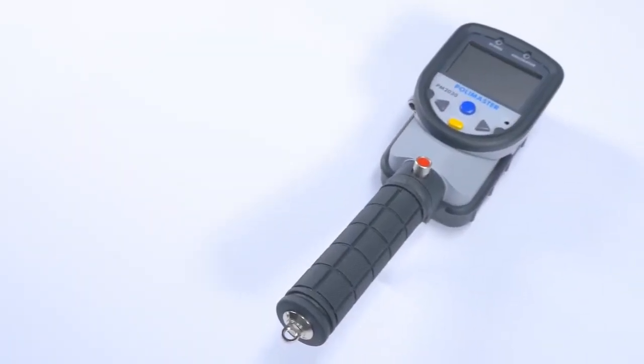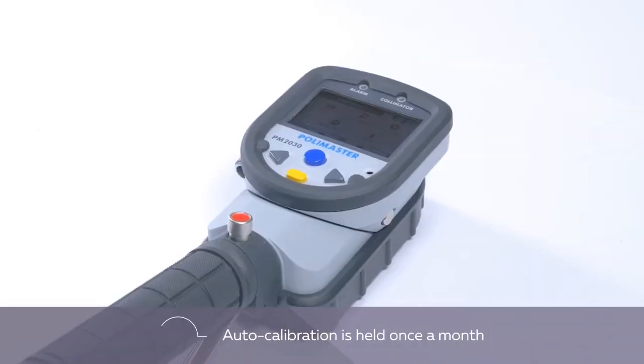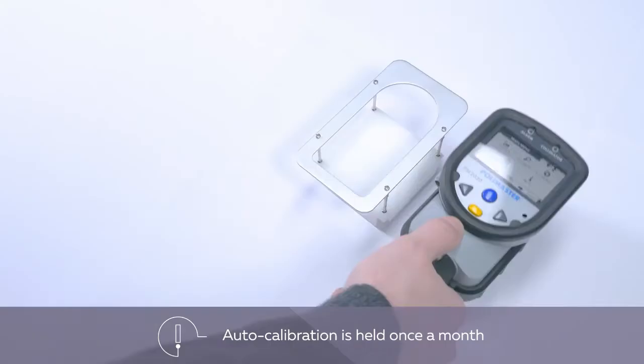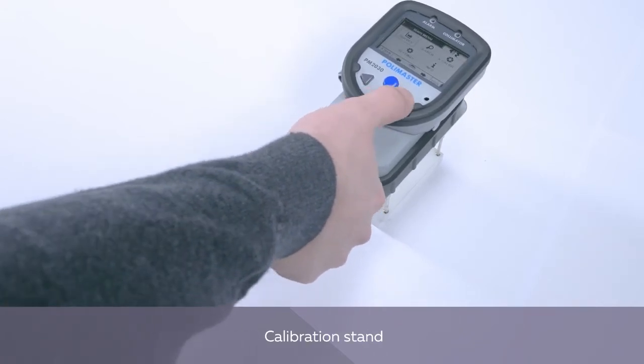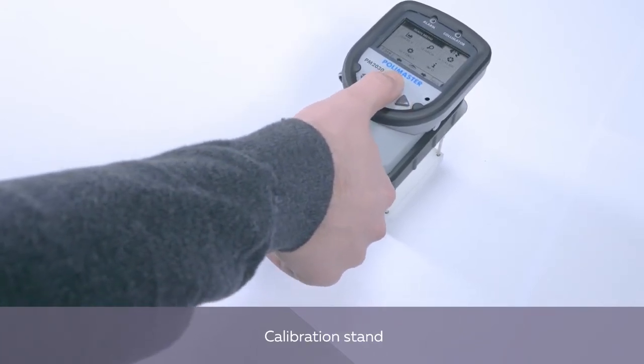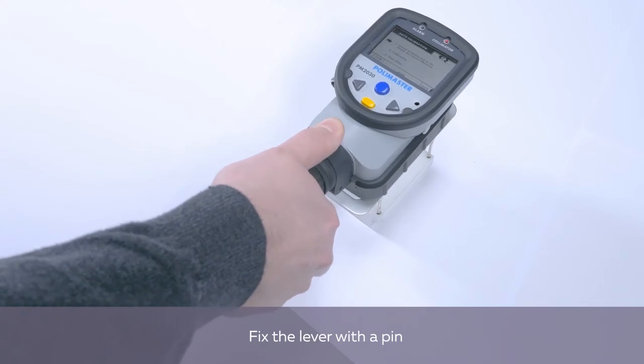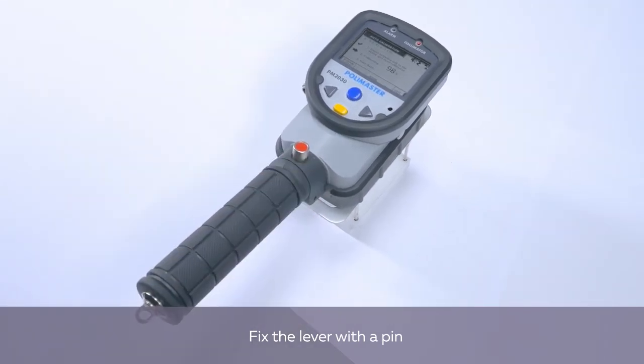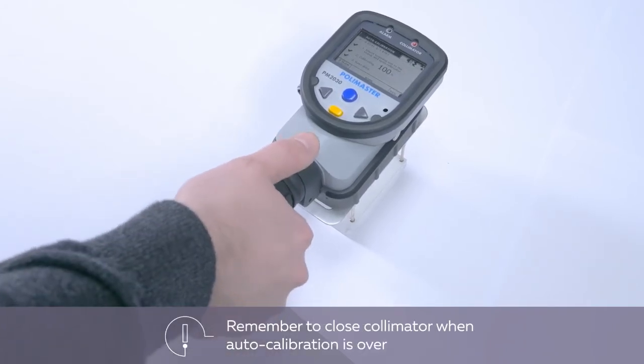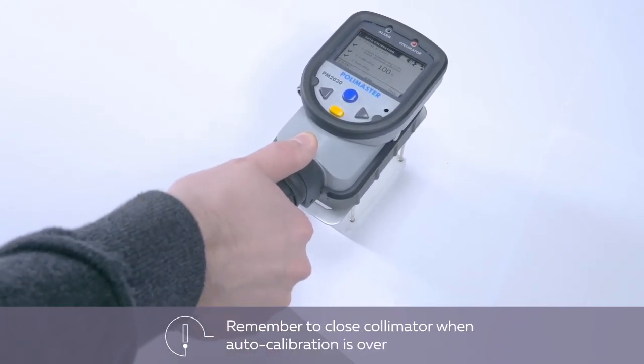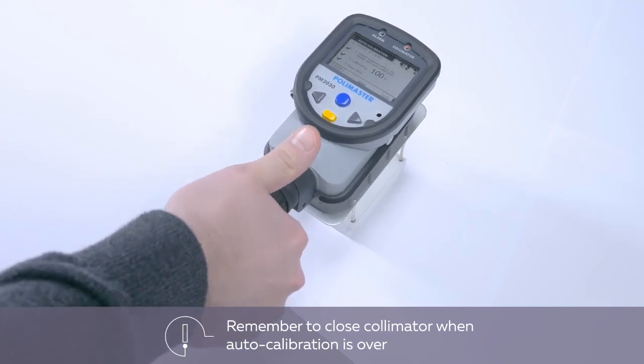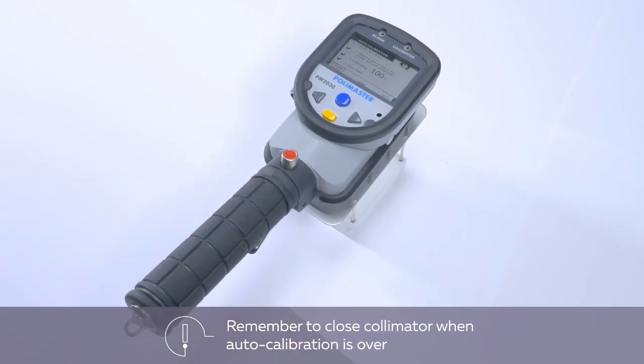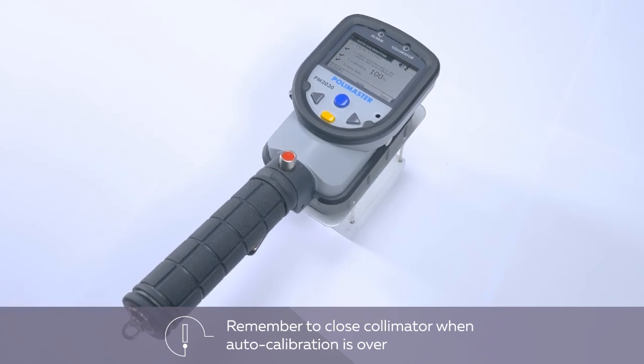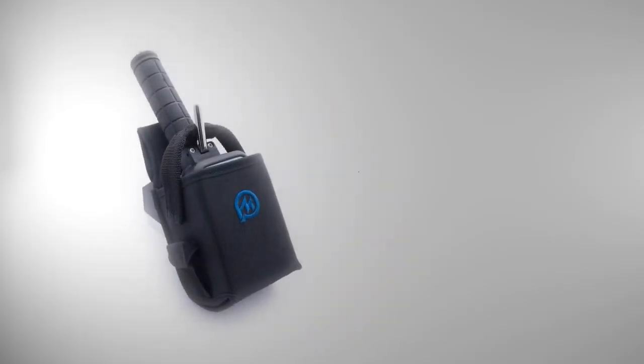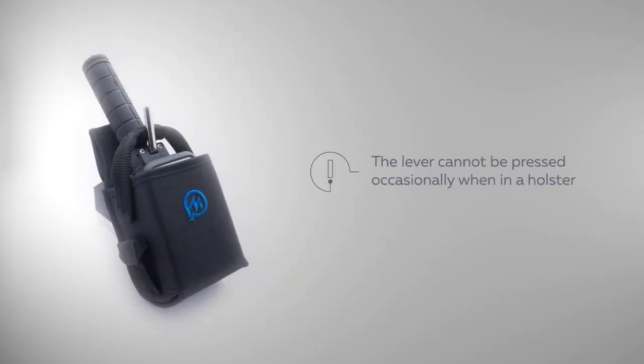To maintain correct operation of the device, it's necessary to carry out the auto-calibration at least once a month. Put the device on the calibration stand, turn the detector on, and choose the required mode in the menu. Press and fix the lever with a fixing pin to open the collimator. Then, monitor the auto-calibration status on the display. When operation is completed, it's required to close the collimator. If everything's done correctly, the sign of the radiation danger disappears on the display, and the collimator status indicator is deactivated. A fixing belt with a special aluminium insert prevents the lever from being pressed occasionally.